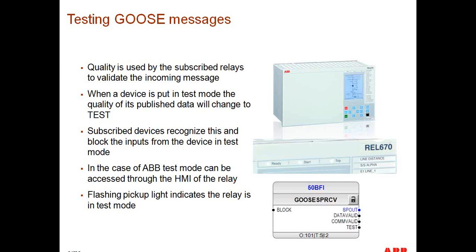In the case of ABB relays, we provide visual indication in the HMI that a particular device is in test mode, so that once testing is completed, there is visual indication that that device needs to be taken out of test mode so that normal operation of the system can resume.